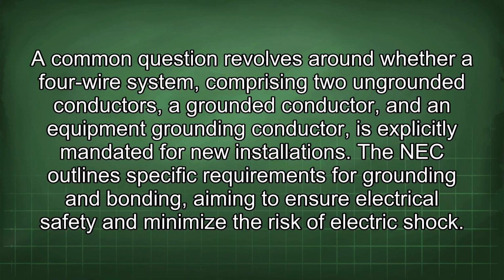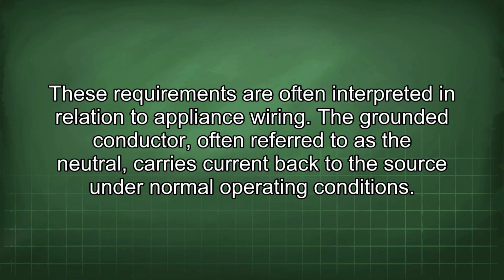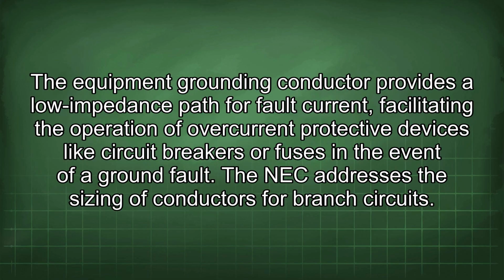The NEC outlines specific requirements for grounding and bonding, aiming to ensure electrical safety and minimize the risk of electric shock. These requirements are often interpreted in relation to appliance wiring. The grounded conductor, often referred to as the neutral, carries current back to the source under normal operating conditions. The equipment grounding conductor provides a low impedance path for fault current, facilitating the operation of overcurrent protective devices like circuit breakers or fuses in the event of a ground fault.